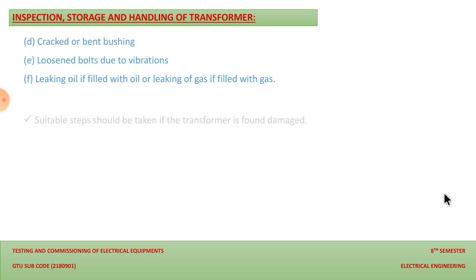Now, suitable steps should be taken if the transformer is found damaged. Which steps should we follow? According to the vendor's manual, if we receive these parts damaged, then we have to call the vendor, and we need to replace all the damaged parts before we use this transformer for operation. If the transformer is found heavily damaged, the manufacturer should be informed immediately, before lifting the core and coil for further inspection.